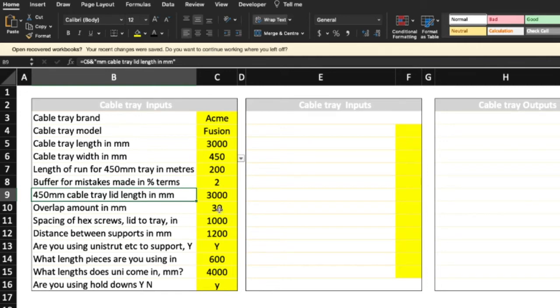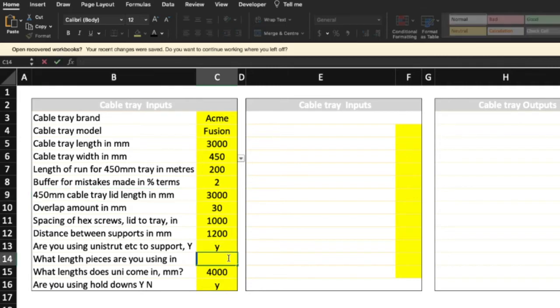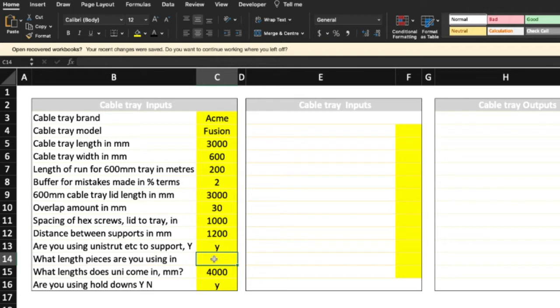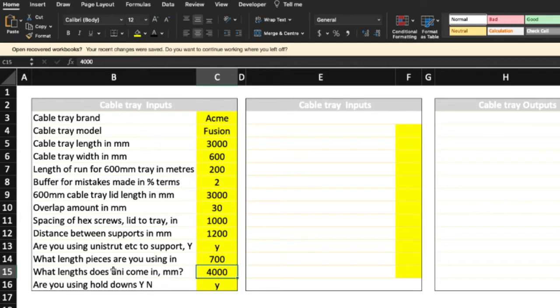Now overlap amount, 30 millimeters. Spacing of hex screws, 1000. Distance between the supports, 1200. Are you using Unistrut? Yes. So what length pieces are you using? This is the lengths that go under the actual tray, so let's say we'll go back to the 600 tray, and let's say we have an overlap of 50 millimeters, so let's say it's 700. And what length does the Unistrut come in, or the structural support using, and you can input what you like. And are you using hold downs, yes or no?